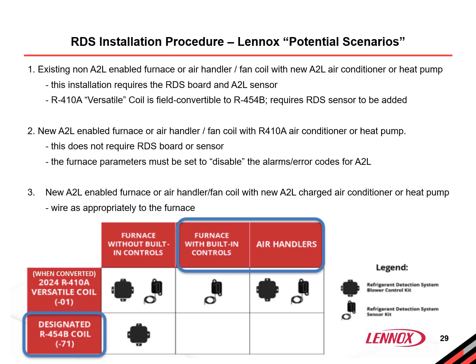Scenario 3. And finally, we have a fully A2L compatible system. Both the furnace and the outdoor unit are designed for A2L refrigerants. In this case, proper wiring is more critical to ensure seamless integration. The RDS components will already be part of the system. However, double check that everything is configured and wired correctly to meet current safety standards.